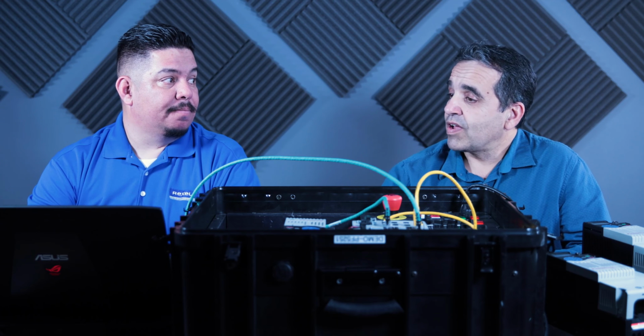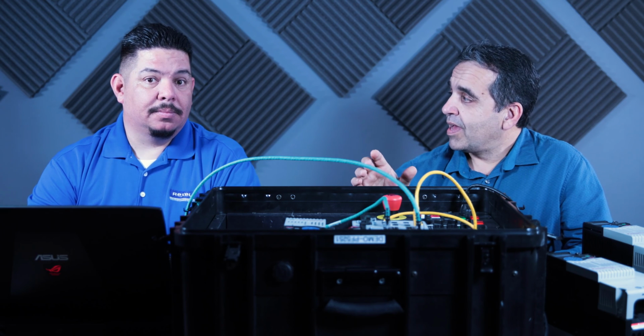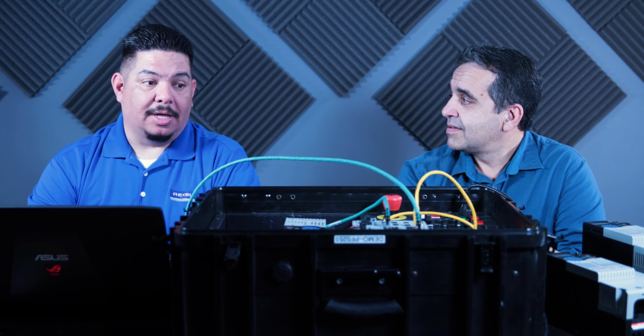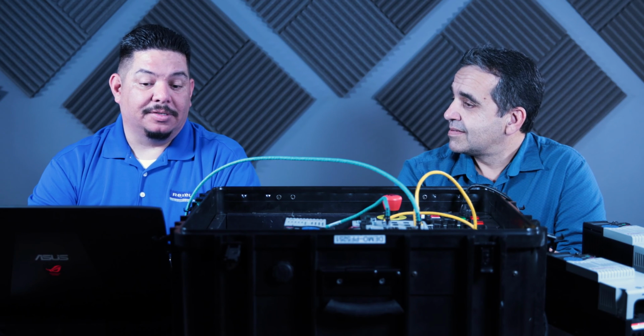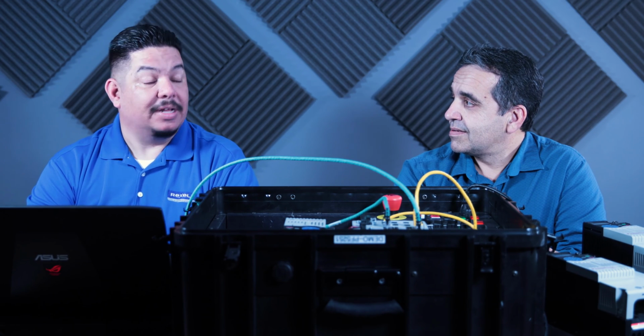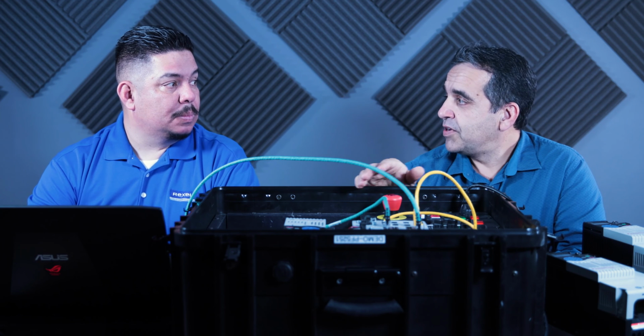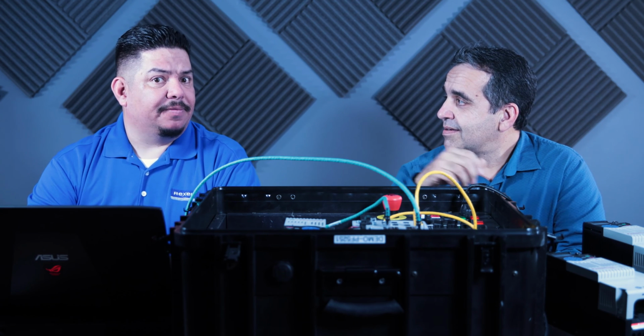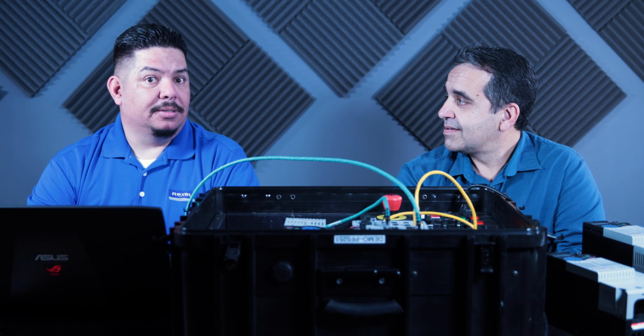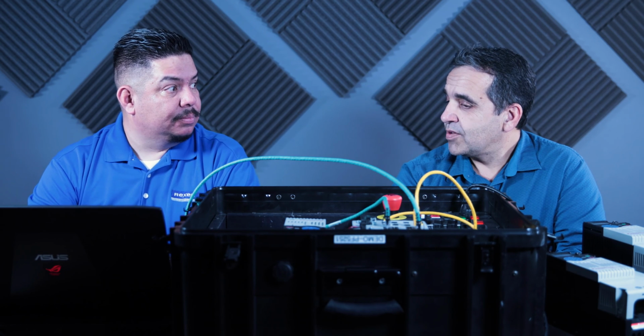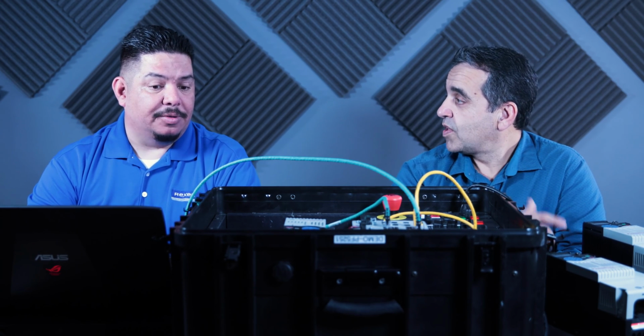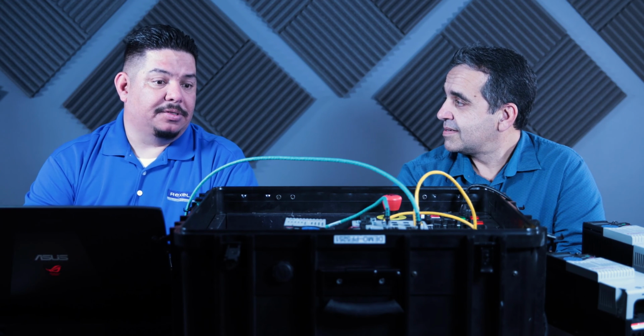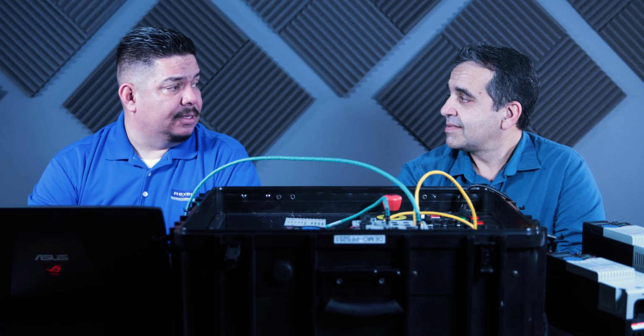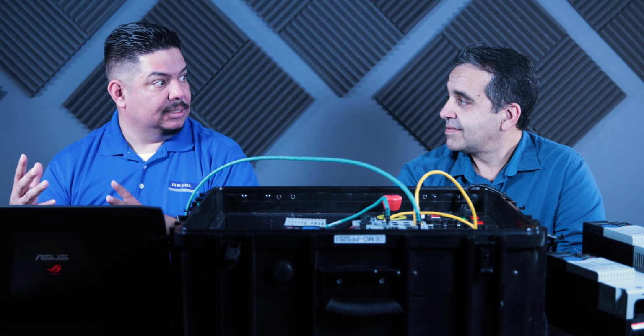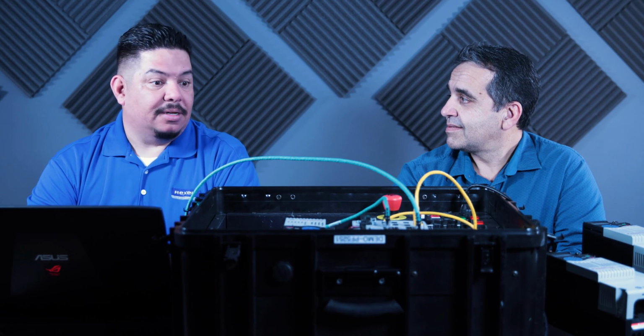And we can go straight from our computer and program drives. We can upload and download parameters, save parameters onto our laptop through that software, as long as we're Ethernet connected. Different types of communication are available, serial and Ethernet, both. They make USB cables for the older drives, the 4s and 40s. It's a separate purchase. But if it's Ethernet, any Ethernet cable will work.